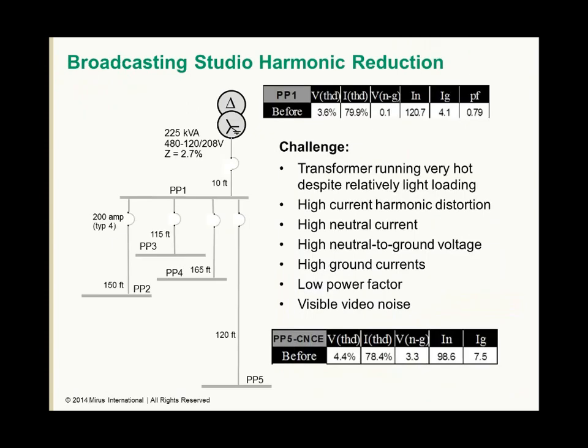Facilities with high concentrations of phase-to-neutral nonlinear loads, such as broadcasting studios, can be subject to problems related to third harmonics. At one such facility, the transformer was running extremely hot, despite being lightly loaded, and video noise was ruining the transmission quality. In addition, measurements showed that current harmonics, neutral current, neutral to ground voltage, and ground currents were all high, while power factor was low.